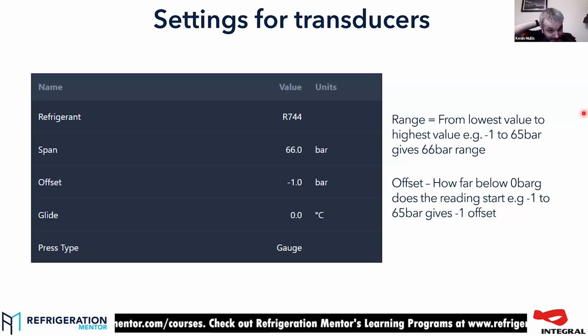So the next slide that Trevor's put up there is how you set up the transducer. And the settings are virtually the same, no matter whether you're setting it up on the fixture controller, on the rack controller, or on a hub. So you need to tell it some important things. You need to tell it what gas you've got, because obviously it needs to work out the evaporating temperature for you. You need to tell it what pressure range the transducer covers. You need to tell it whether it starts at 0 or not.